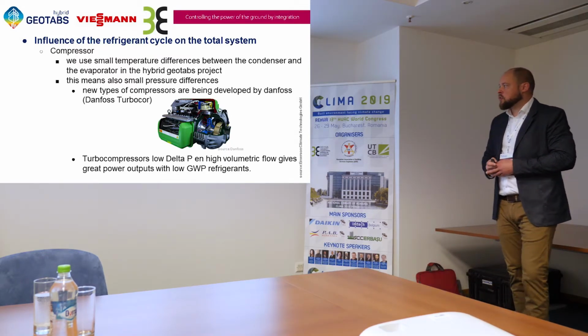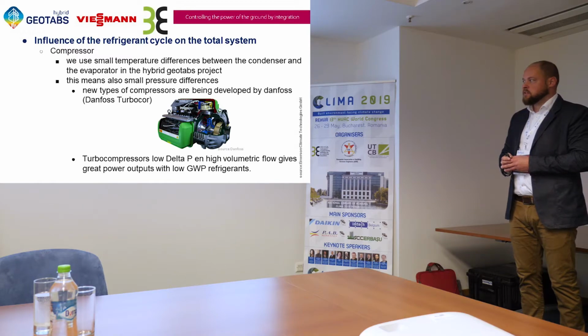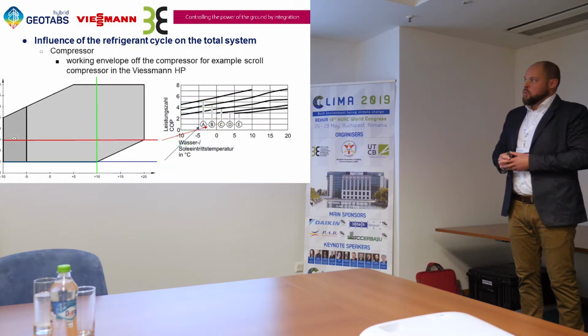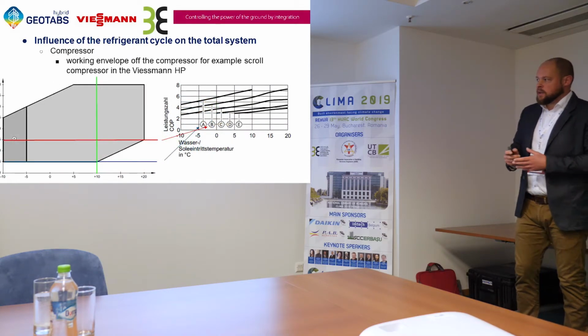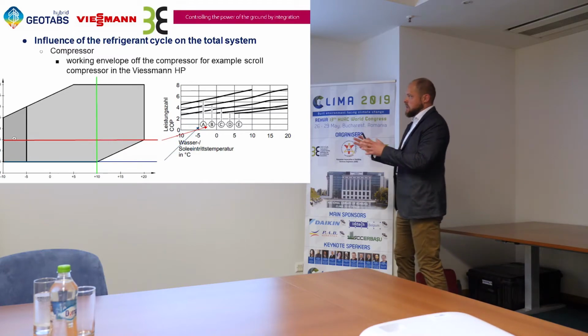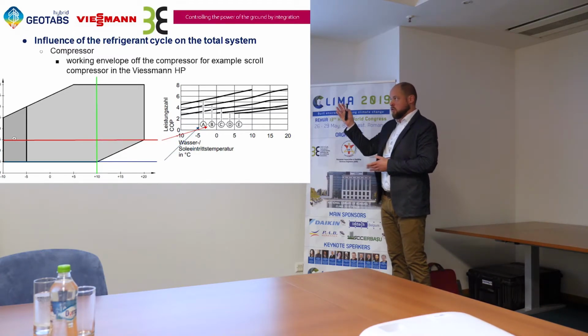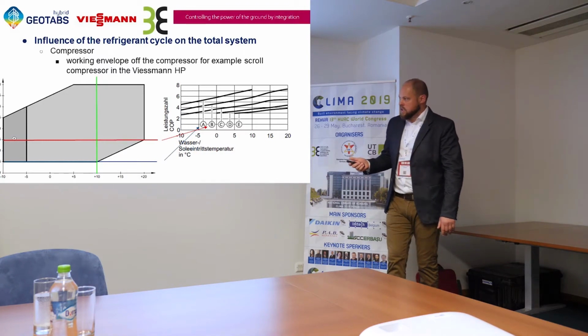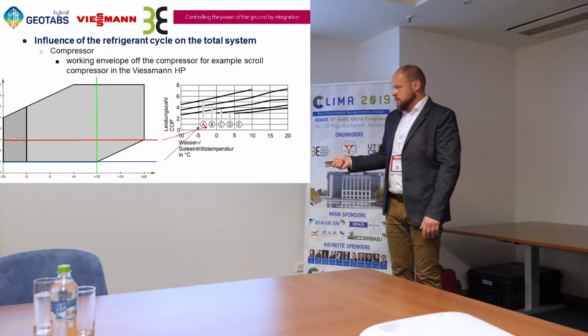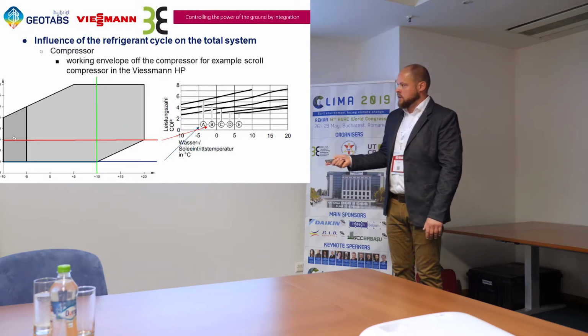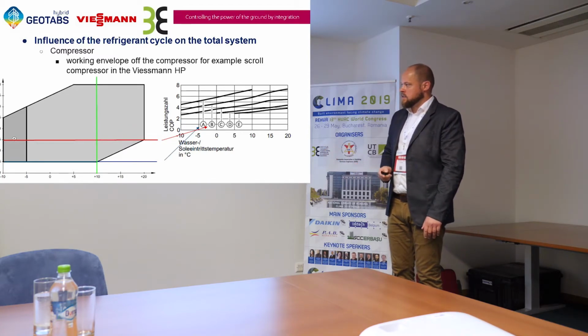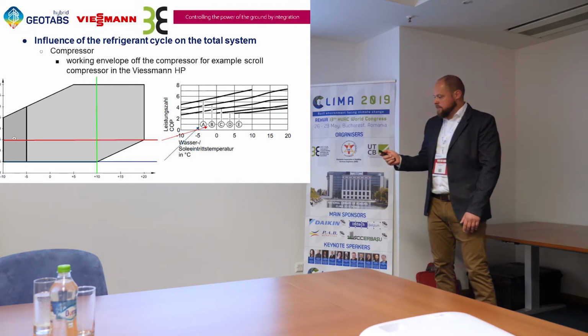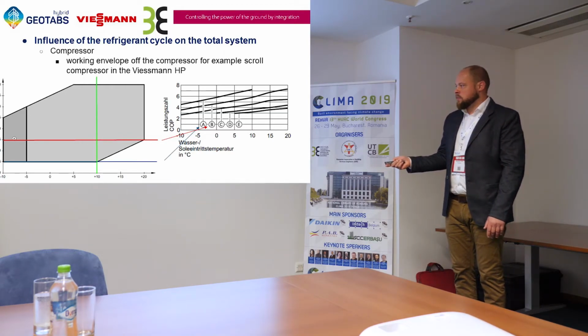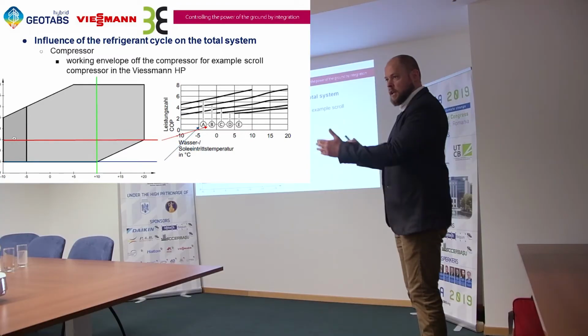Danfoss has developed a Turbocor, and it has been in development since 2017. What's the working envelope of a compressor? Why is that important? I have an example of a working envelope of a scroll compressor from Viessmann. What can you see here? This is the input temperature on the source side. This is the secondary temperature on the condensing side. And what do we see? When we have, for example, a source temperature of 0 degrees to about 10 degrees, the minimum departing temperature on the condensing side is 25 degrees. So you cannot go lower than that.